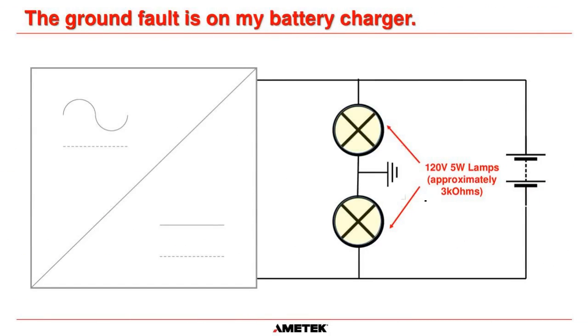Because inside the charger, we have created a ground fault detection circuit. This slide shows you the most basic ground fault detection circuit there is, and that is 2 lamps in series. Let's say, once again, this DC bus is 135 volts, and we have 2 lamps. We're saying they're both 120-volt, 5-watt lamps, which means, if you do the Ohm's law calculation, they're around about 3K ohms.